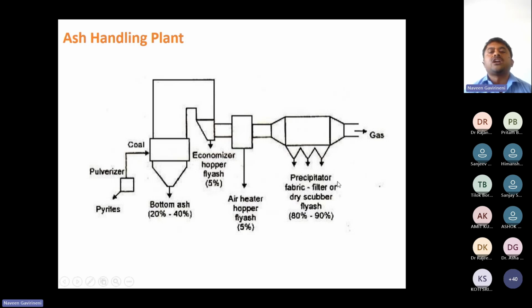So this is the ESP, electrostatic precipitator, which works on the concept of positive and negative ions. There are two types of arrangements: one is the collecting electrode and the other is the emitting electrode. The collecting electrode collects the dust particles, and the emitting electrode strikes the plates and the dust is collected in these hoppers. Based on the capacity of the plant, the hopper arrangement and the number of hoppers vary. Finally, the gas goes to the atmosphere through the chimney.